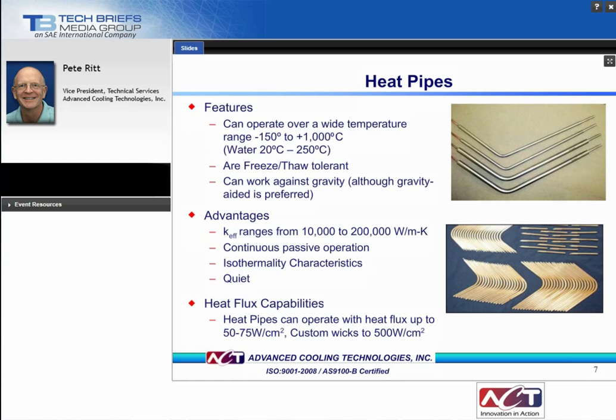So now that we know a little bit about heat pipe operation, let's look at how this can be put to use. First of all, with different combinations of envelope materials, wick structures, and working fluids, heat pipes can be used over a wide temperature range, from cryogenic to liquid metal, from around minus 150 to over 1,000 degrees C. We'll look at some high temperature heat pipe options later on. Because they are sealed vacuum devices, some working fluids can operate well beyond their nominal boiling point. Water, for example, can be an effective working fluid from 20 to 250 degrees C. By controlling the amount of working fluid and selecting the appropriate wick structure, heat pipes can restart operation after freezing. They are freeze-thaw tolerant. Also, with the right wick structure, heat pipes can operate against gravity. Typically, heat pipes can transfer heat 8 to 10 inches against gravity, although gravity-aided operation is generally preferred.